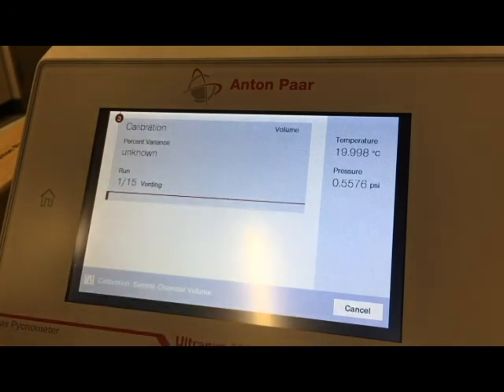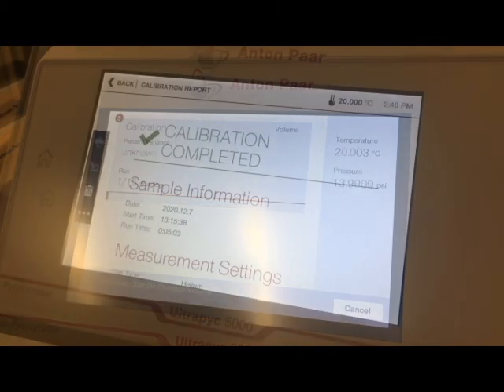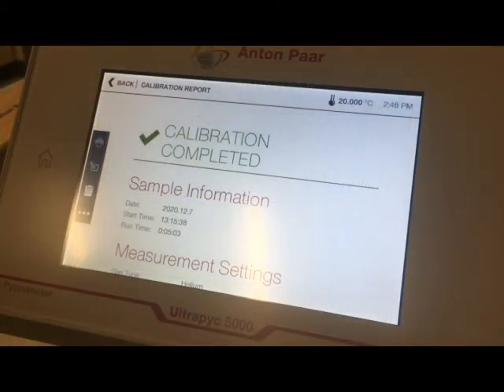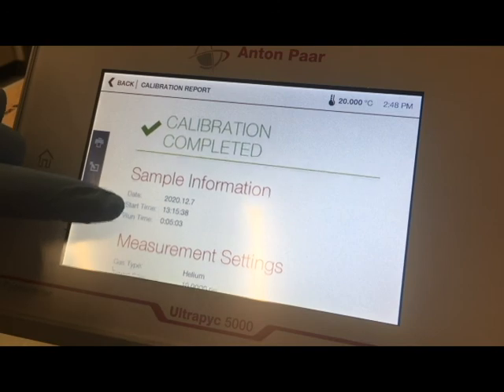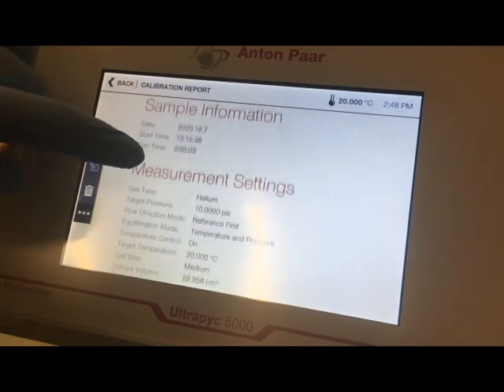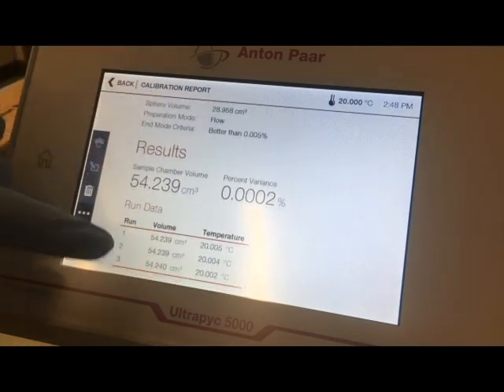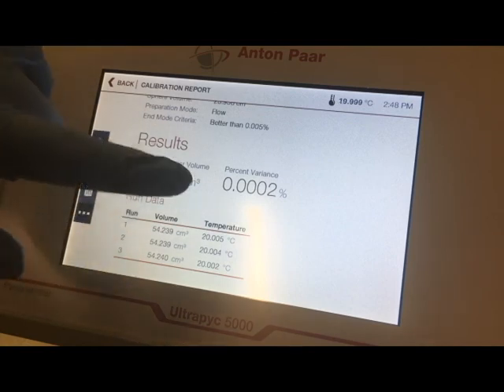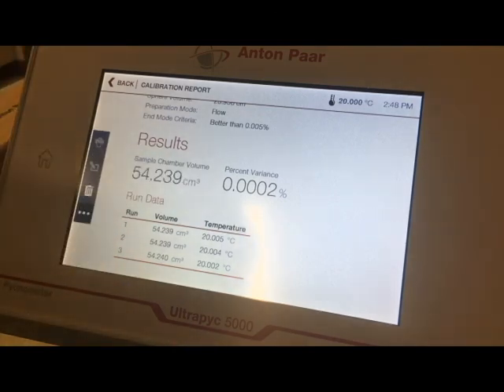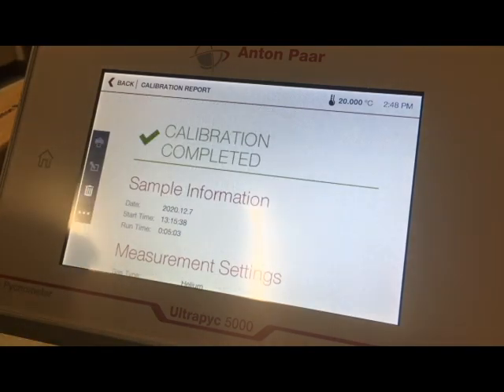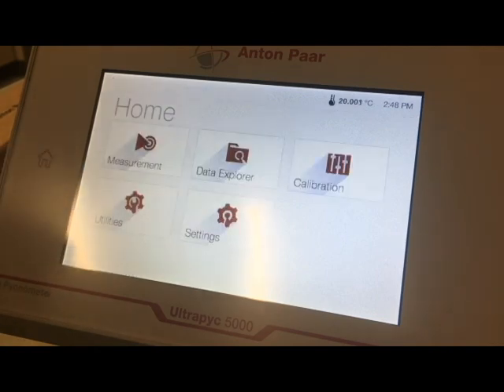So I'm going to hit continue, and now it's going to run our calibration test. This typically runs less than half an hour. If it runs longer than half an hour, it is always less than 1 hour. Here you can see the calibration is complete. It took about 5 minutes to run, as you can see here. You can review the measurement settings and look at the results. We have a pretty good percent variance here. Successful calibration. We're going to go back to the home page now.